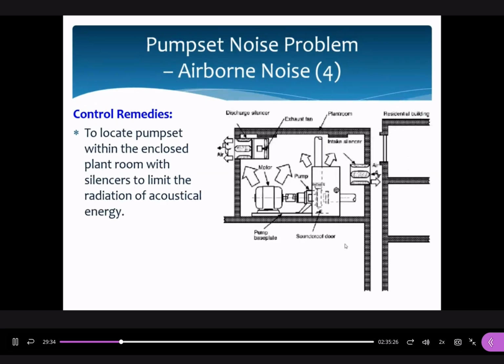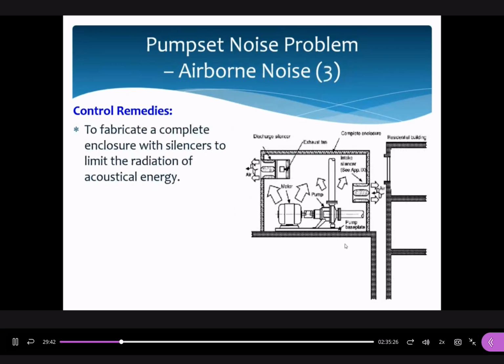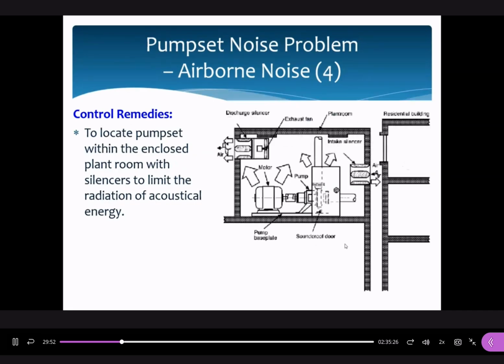Another option is to locate the pump set within an enclosed plant room. This is essentially similar to the previous one - also a complete enclosure, but the size is getting bigger or larger when we use a plant room. But comparing these two figures, we still install the discharge silencers for both provisions.